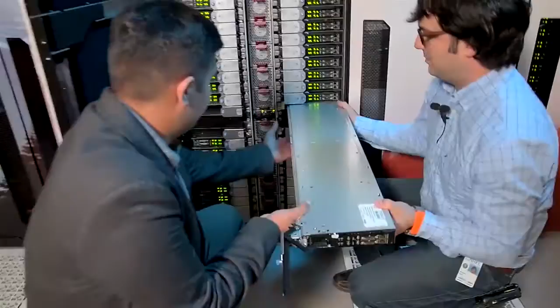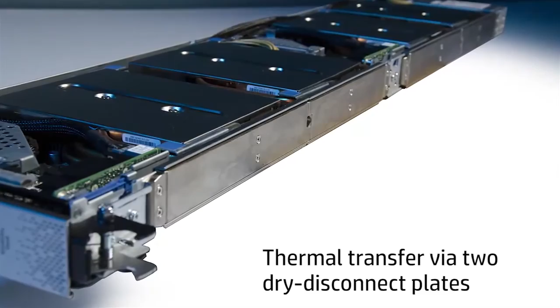And what you see right here is that dry disconnect system, and that's the thermal transfer technology for that tray. What you see in that tray are basically 2 component-level liquid-cooled servers. Each of them is fully independent, so there's the front one and the rear one. But there's no water in the server.